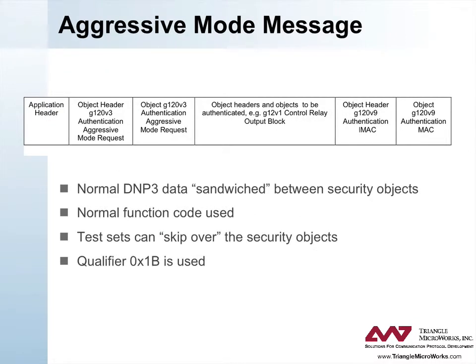This diagram illustrates how objects and headers are arranged when using aggressive mode. The application header and the objects between the aggressive mode request and MAC objects are standard DNP3 objects. The qualifier used for the authentication objects is 1B-hex, which permits test sets that do not understand the security messages to skip over the unknown objects if they choose.